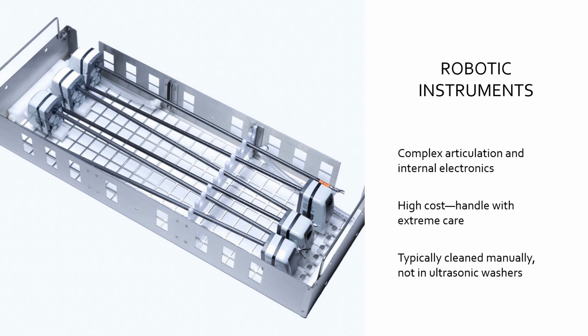After you clean them and you flush them and all that, they can go in an ultrasonic, but it has to be an irrigating ultrasonic. So there's got to be a hose that hooks up to it, to where when it's running, it's flushing water through that port. Now, according to some of the IFUs, depending on the maker of these, after the ultrasonic and after you rinse them and dry them off, they can just be passed through the window into the clean side.